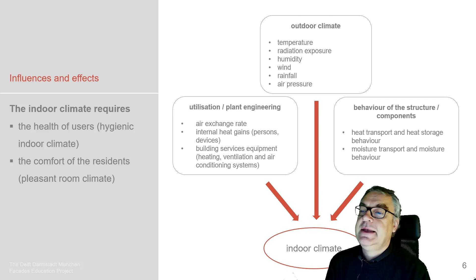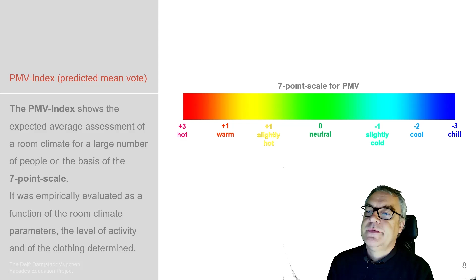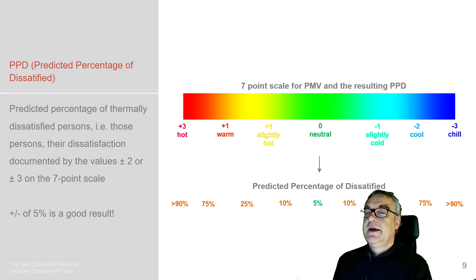So the PMV index, the predicted mean vote, so what do people like most, what do people normally expect to be the most interesting part. It's a 7-point scale, too hot till too chilly, which we define, versus the PPD, the predicted percentage of dissatisfied people, in which we have a plus or minus, too hot, too chilly as well, and then a number of dissatisfied people. And you can imagine not everybody's going to be happy in a space when you engineer it. It's kind of impossible. So if you end up with a plus minus of 5% being dissatisfied, too hot, too chilly, we actually did good engineering. So it's impossible to get this down to zero.